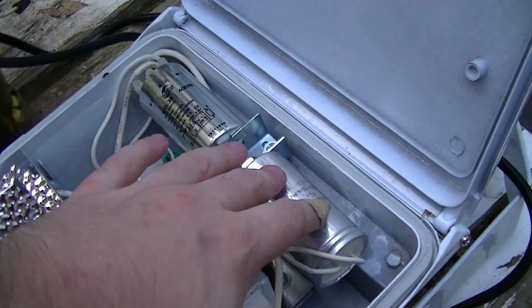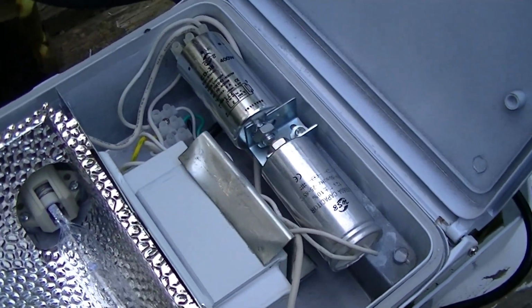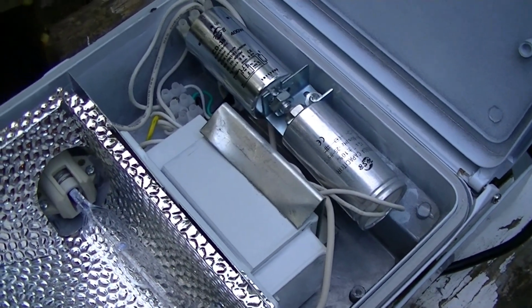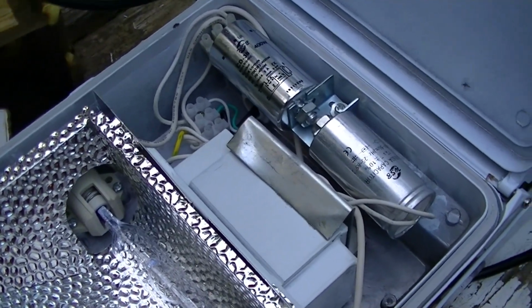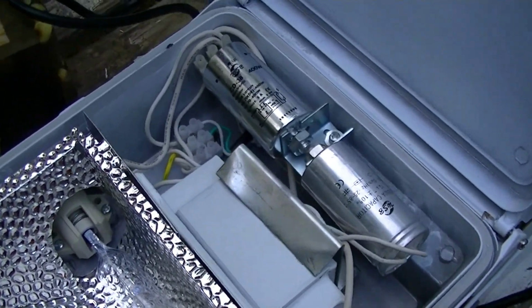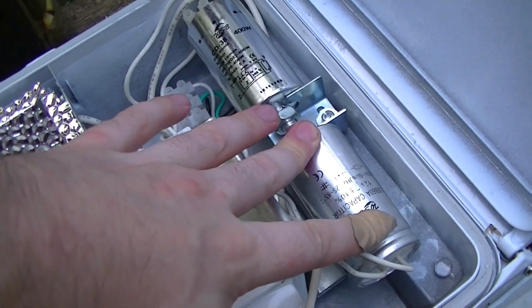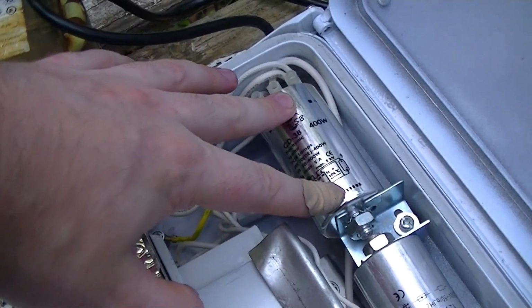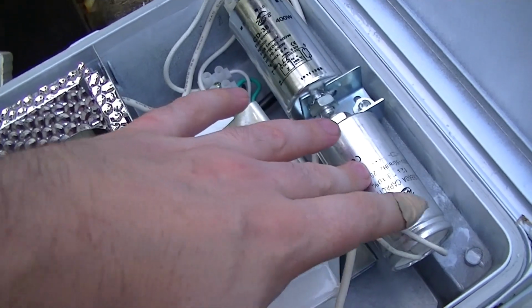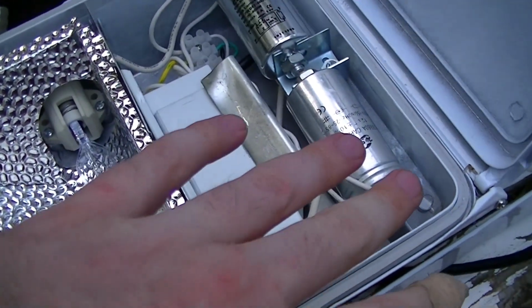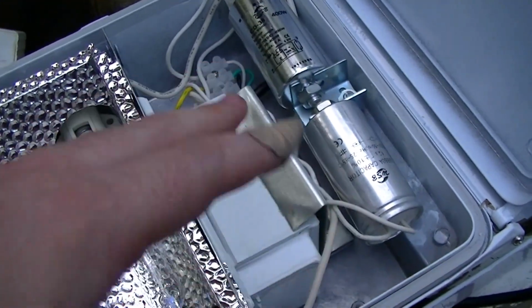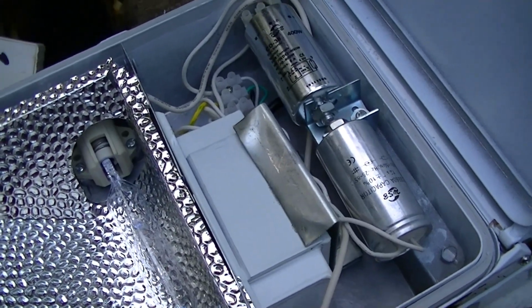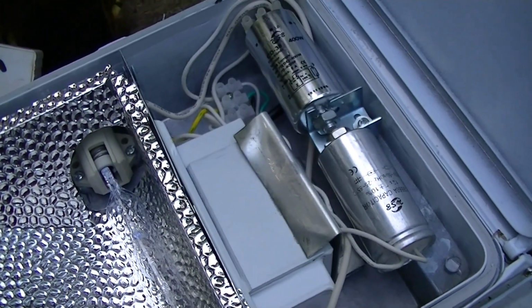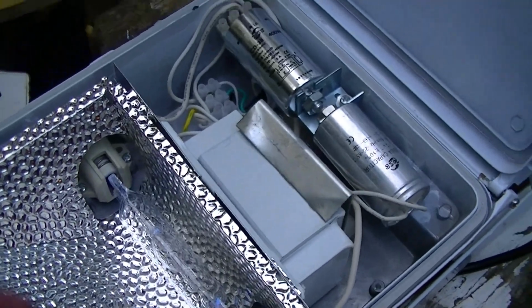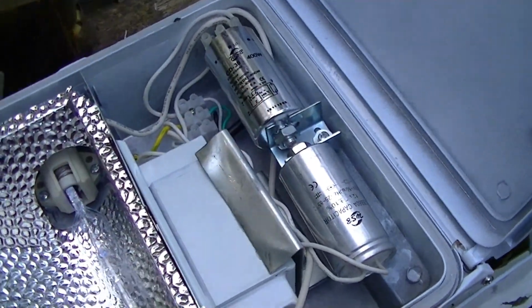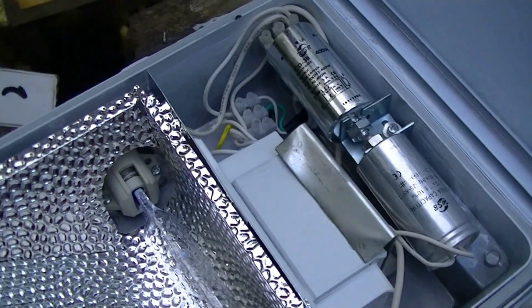So this capacitor does do something, although it really kind of serves as much for EMI suppression, and also this provides a shunting path for current spikes from the action of the igniter, so that way those spikes don't really carry on to other stuff on the line, and especially in the case of electronic anything, ballasts, electrical equipment, what have you, possibly damage it. So the capacitor is really doing kind of triple duty. Power factor correction is only part of it.